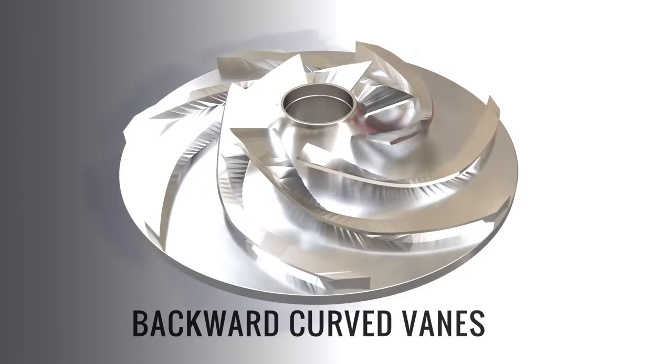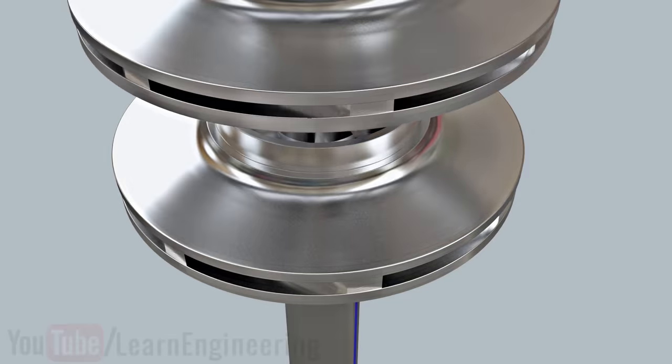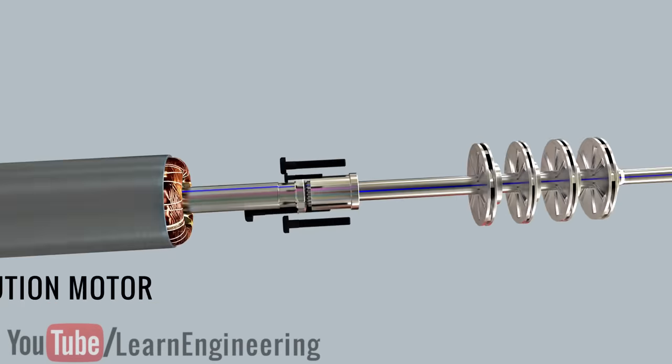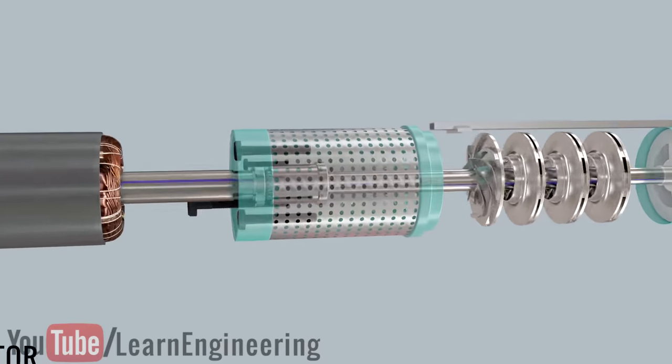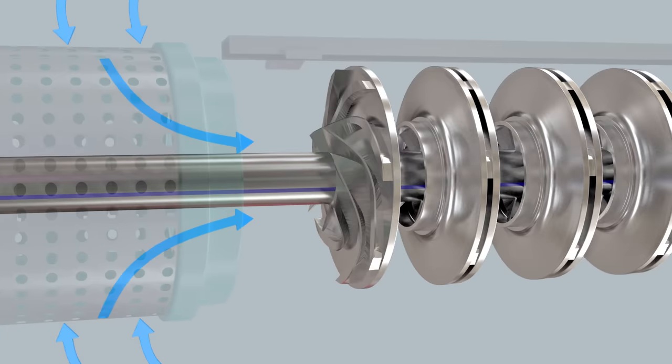The impeller blades are the backwards curve type. Here, many of the impellers are connected onto a single shaft, and this shaft is driven by an induction motor. The water enters through the eyes of the impellers, and they are then thrown out radially due to centrifugal action.